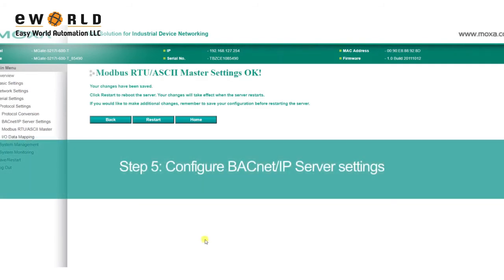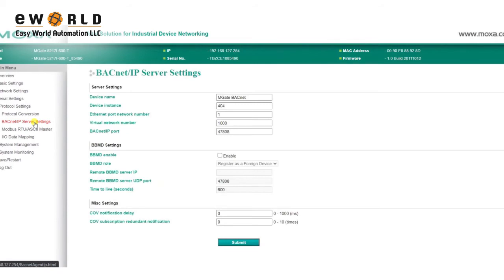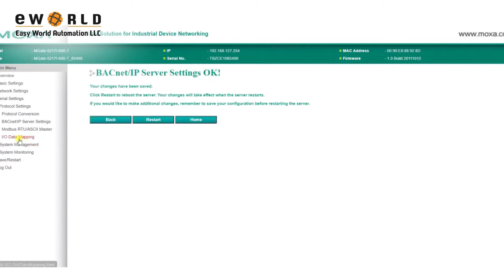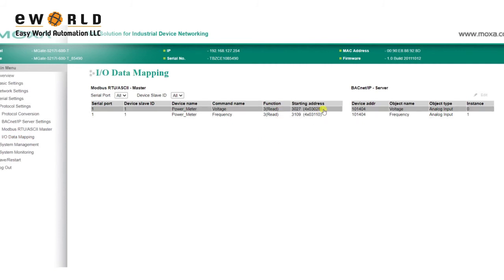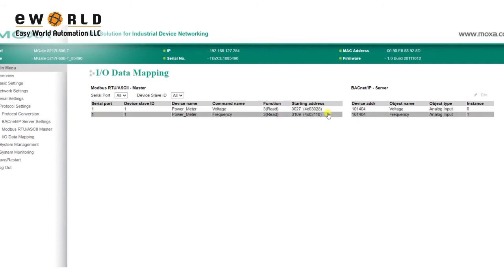The MGate will also act as a BACnet IP server, and in BACnet IP server settings, you can configure basic parameters, such as device name, device instance, and the BACnet IP port. Now, when we go to the IO data mapping page, we can see that our voltage and frequency information can be read through analog inputs 0 and 1.